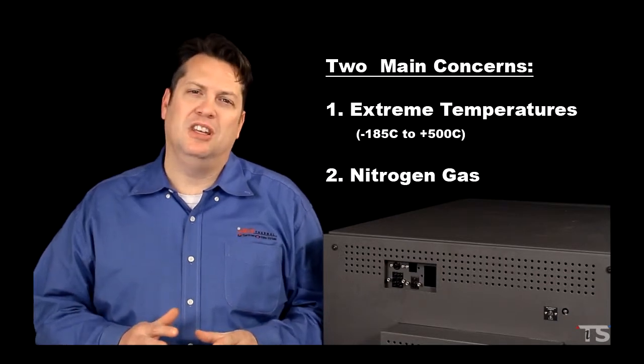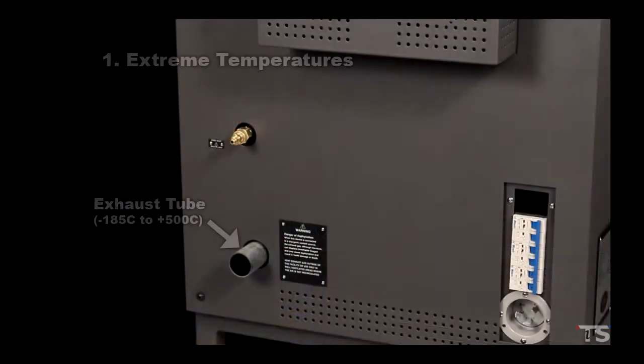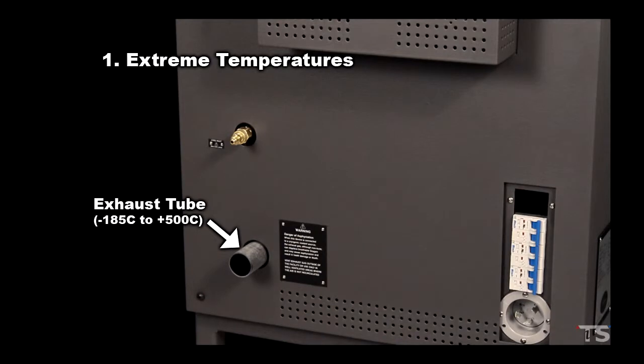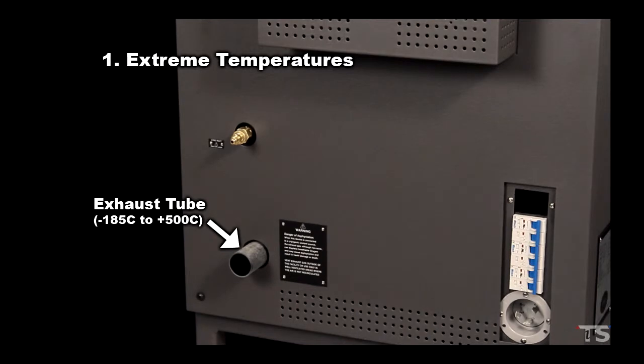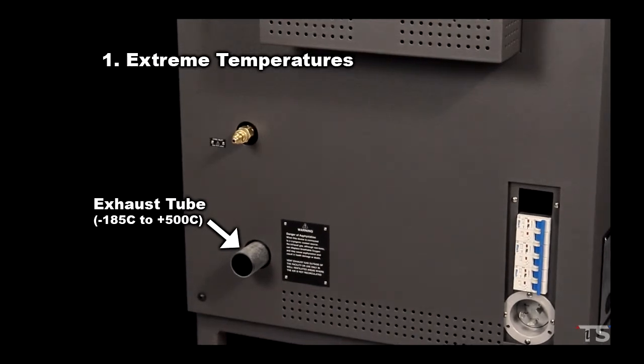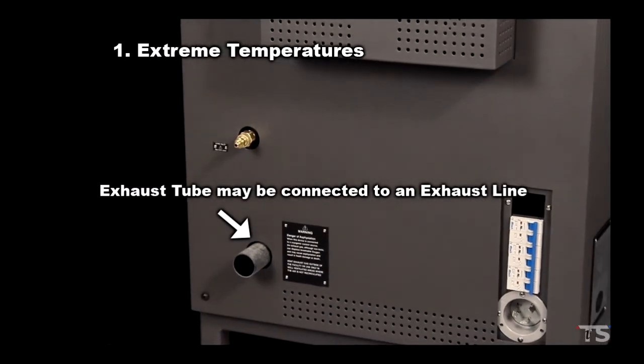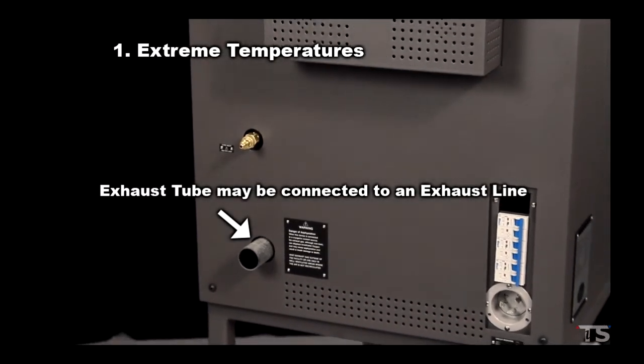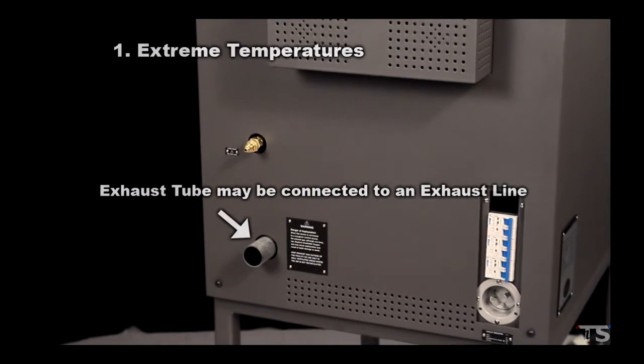Extreme temperatures are pretty easy to understand. The exhaust coming out of your chamber's exhaust tube can be as hot or cold as the temperature rating shown on the equipment name plate. Whether your chamber exhausts freely or is connected to an exhaust line, you must be aware of the extreme temperatures that are present.